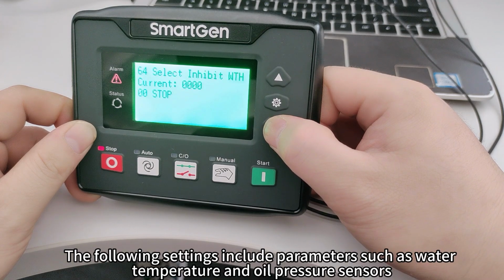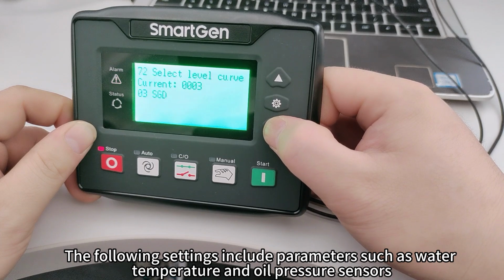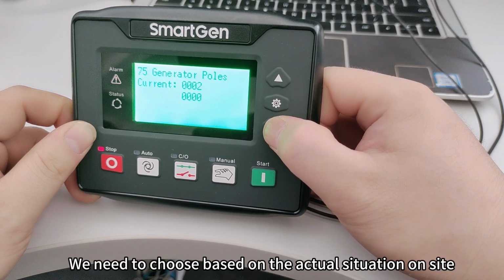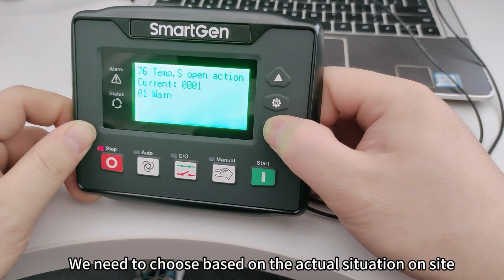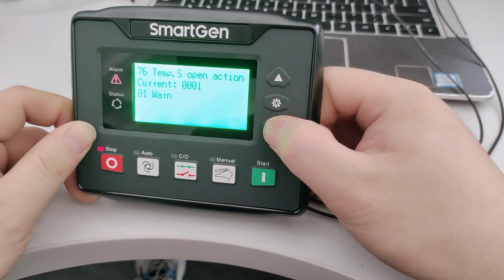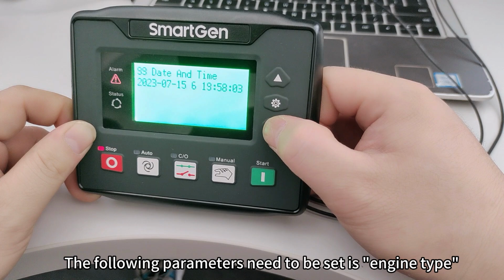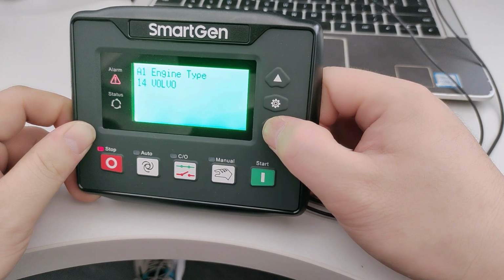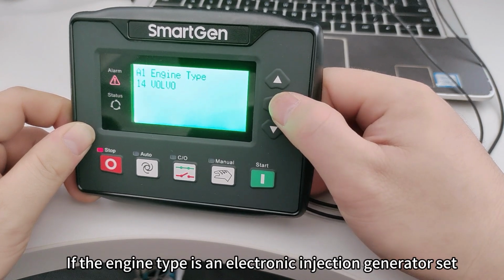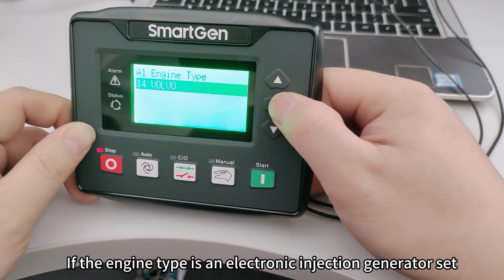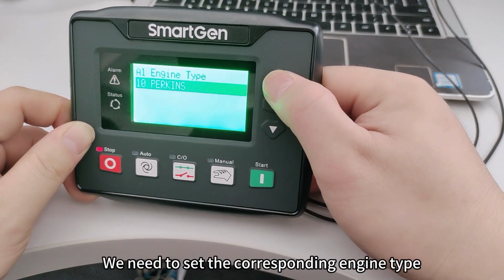The following settings include parameters such as water temperature and oil pressure sensors. We need to choose based on the actual situation on site. The following parameter to set is the engine type. If the engine type is an electronic injection generator set, we need to set the corresponding engine type.